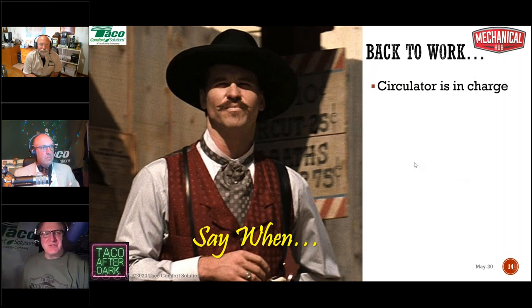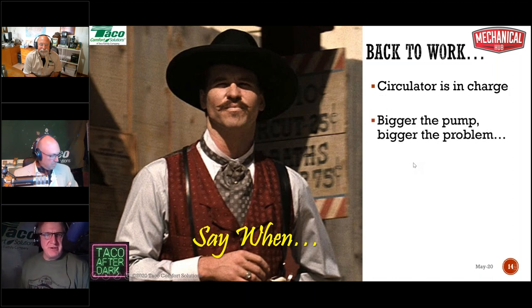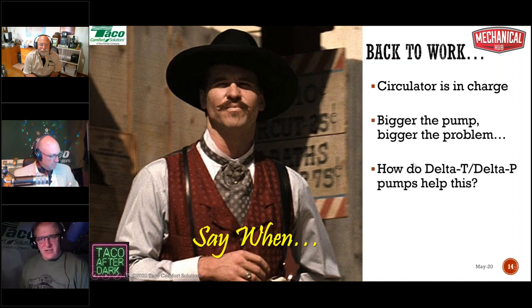So, back to work. Remember, the circulator is in charge, and the bigger the pump, the bigger the problem. The question we want to address now is, how do variable speed pumps, whether they're delta T variable speed pumps or delta P variable speed pumps, help this problem? Neither is going to solve it or make it go away entirely, but both have the ability to mitigate some of that short cycling when they're applied properly. So let's take a look.